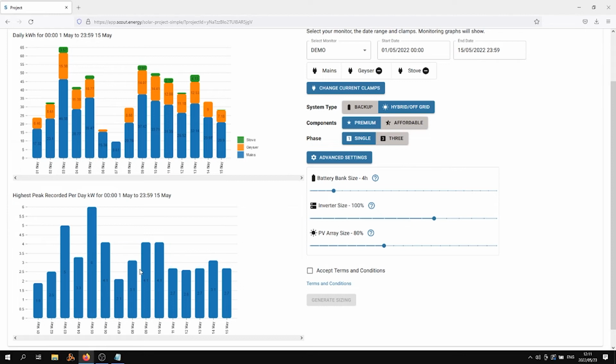This is also where you need to talk to the client. If you have 2 outlying days, like maybe the guy was welding or he started a pool pump or something that caused this peak, where all these other days, you can see on the left, he can actually get away with a 5 kVA system if he manages his power correctly. So again, your input, you decide.